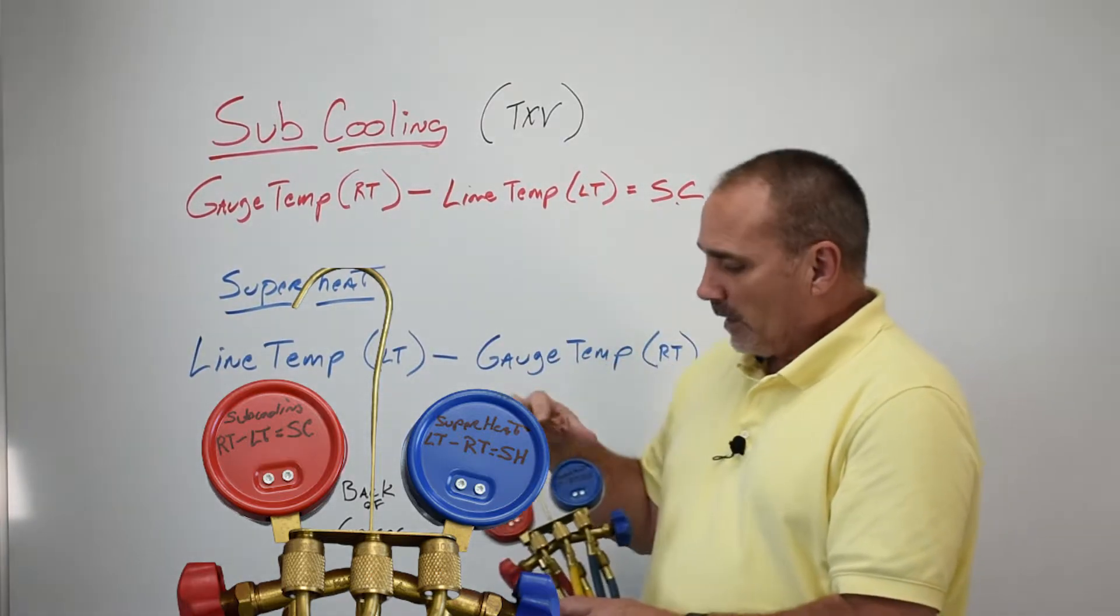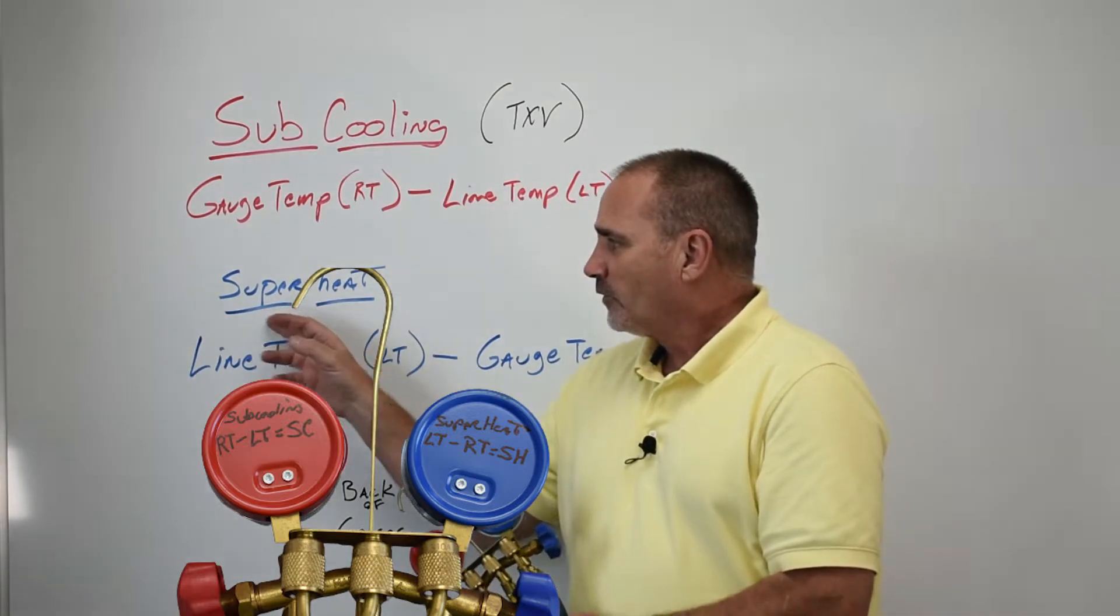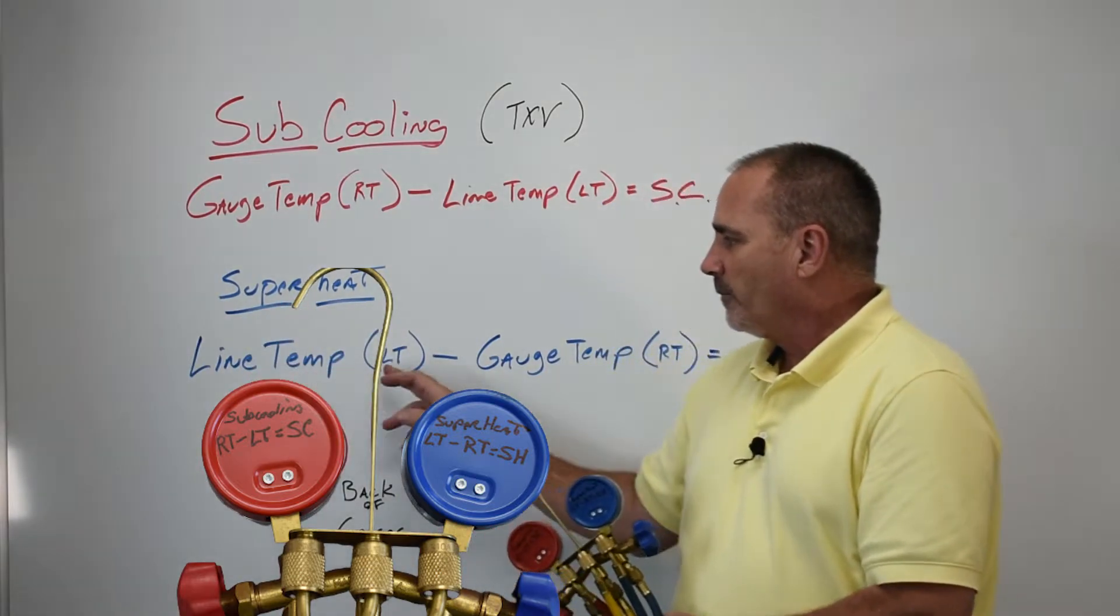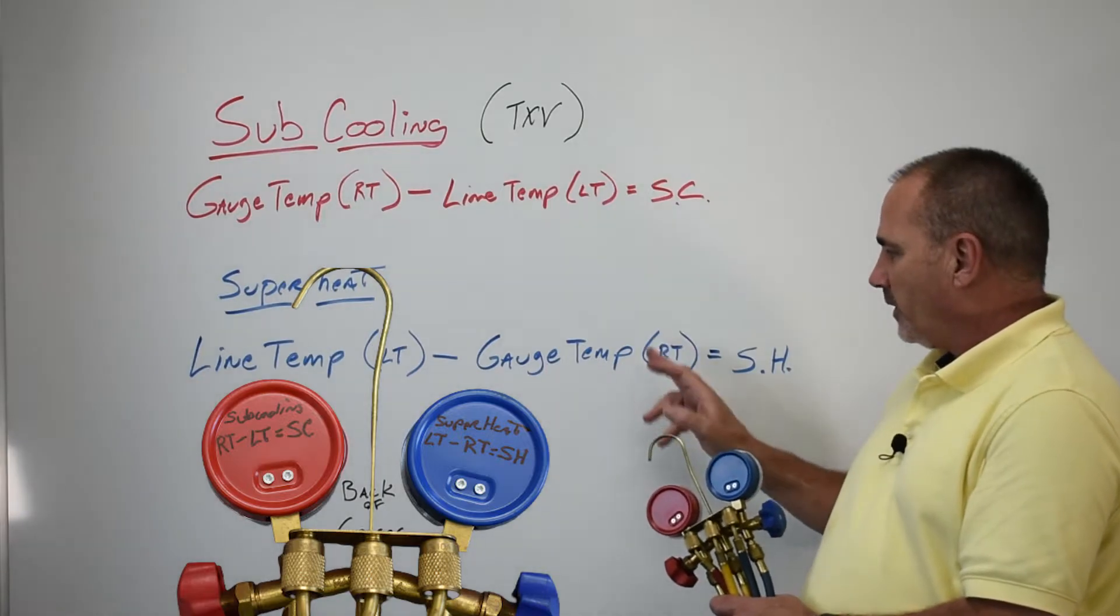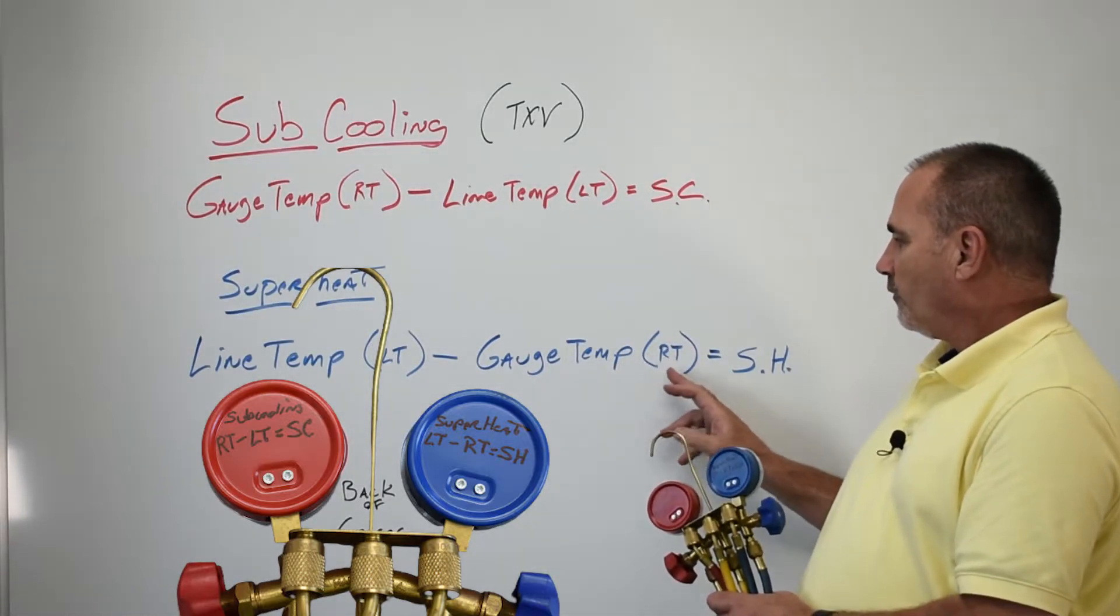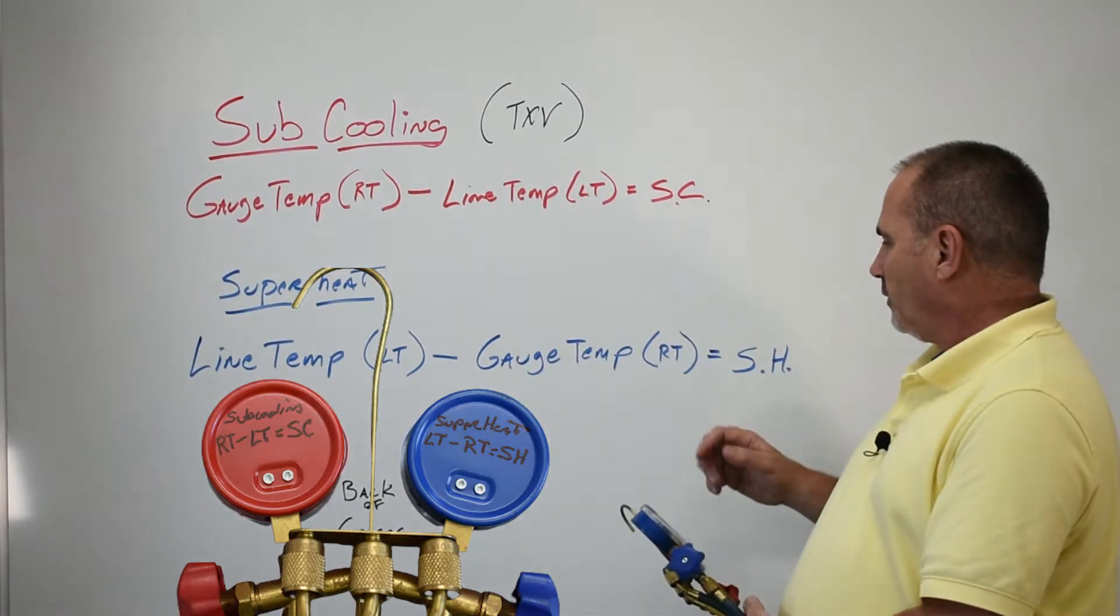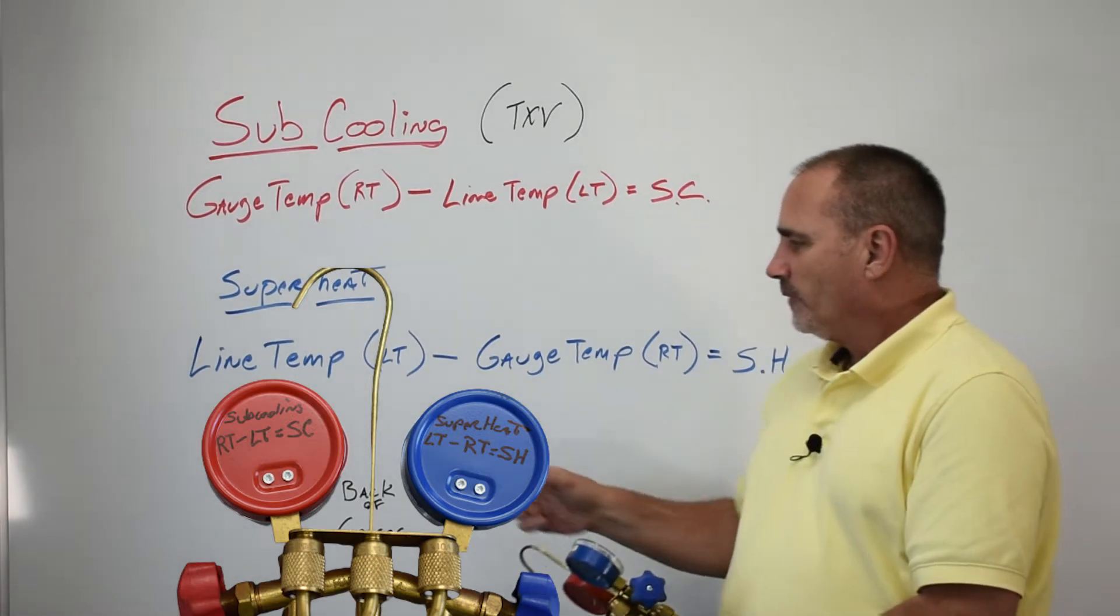And then on the suction side for superheat: line temp (LT) minus gauge temp (again I refer to it as RT for refrigeration temp, depending on what ring you're using) equals your superheat.